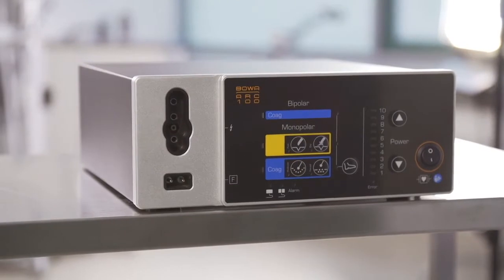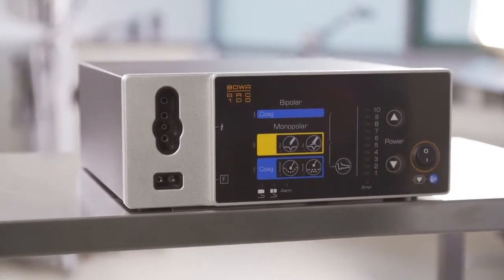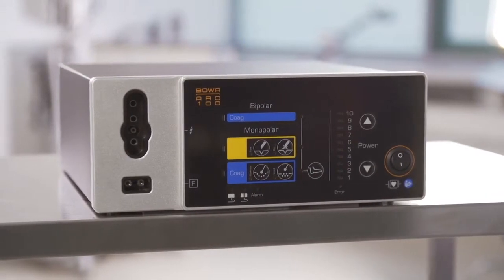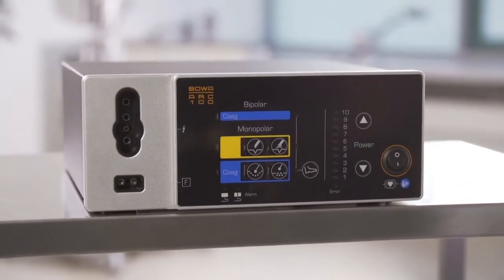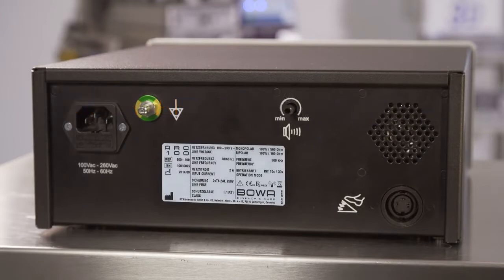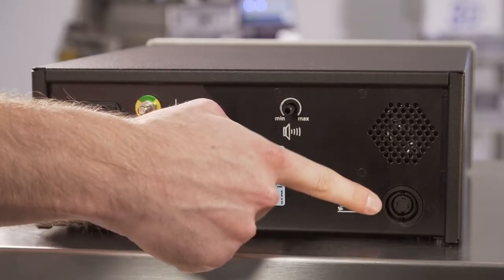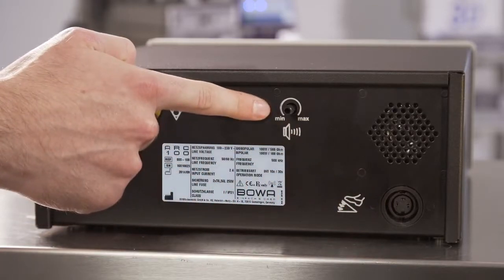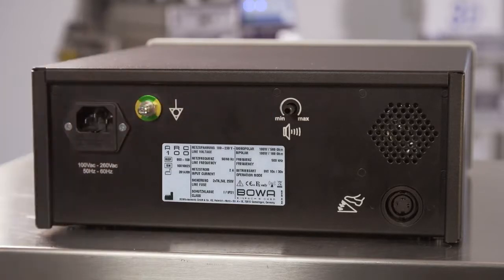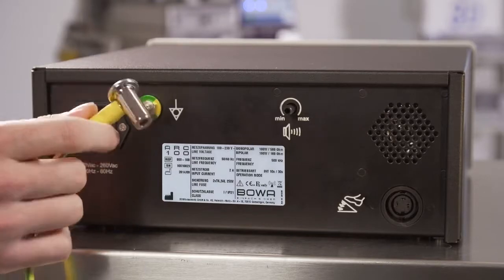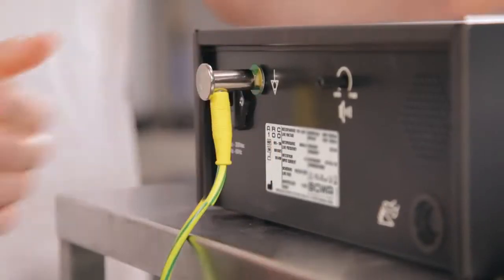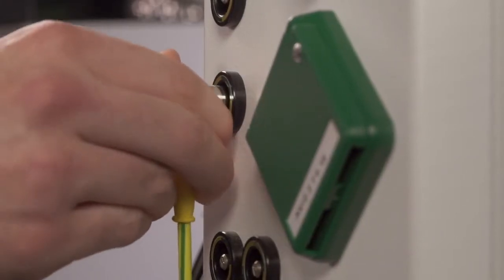Place the ARC 100 in front of you on a horizontal surface so that you can see the display at all times. Do not cover the display during operation. Make sure that the on-off switch is set to 0. On the rear is the connection for a possible equipotential bonding system, the mains cable and a connection socket for the foot switch. The volume of the activation signals in the ARC 100 can be smoothly adjusted using the control dial. For safety reasons, the volume of alarm signals should not be changed. Connect the equipotential bonding of the equipment with the equipotential bonding system of your hospital or practice.